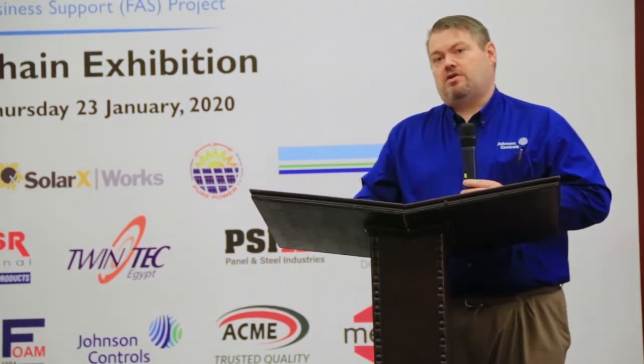Let's talk about what makes an automatic sprinkler work. This is a glass bulb sprinkler — the sprinklers in this room are glass bulbs. Each automatic sprinkler is individually thermally sensitive, meaning each reacts to a fire separately and independently, and only those sprinklers exposed to heat will activate. We have a glass bulb with a fixed volume; we expose it to heat, and using the relationship between pressure, volume, and temperature, as we increase temperature we increase pressure, and as we increase pressure in that fixed volume, we ultimately activate that sprinkler.